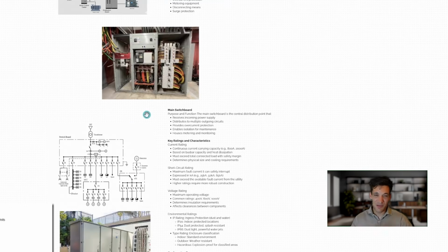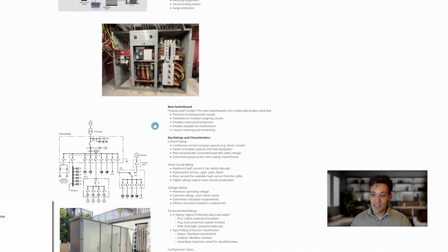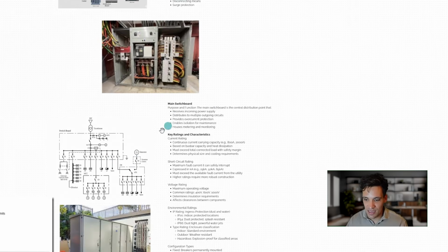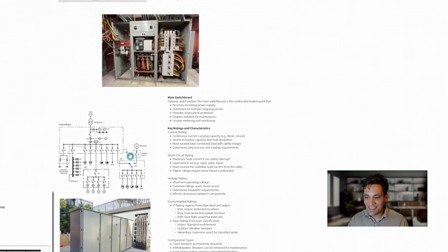The incoming cable might be, depending on the size of the facility, some huge 400 mil or even multiple sets of 400 mil copper cables that terminate in the facility. Then within the main switchboard, we have what's referred to as bus bar, which is a long, thick stretch of copper or aluminium, where the circuit breakers and then the outgoing cables, the smaller cables that connect to all the individual appliances in your facility, connect. A main switchboard, unless they're very big loads, typically won't have loads directly connected to it. It'll connect to sub-distribution boards.